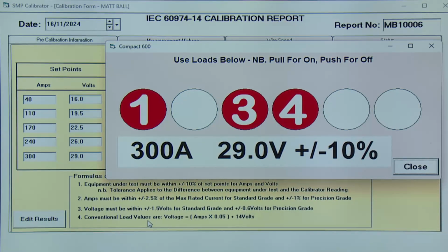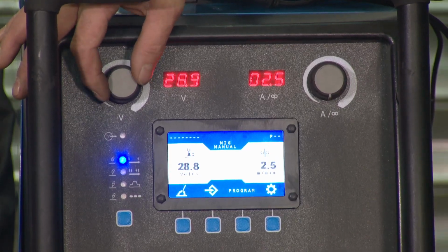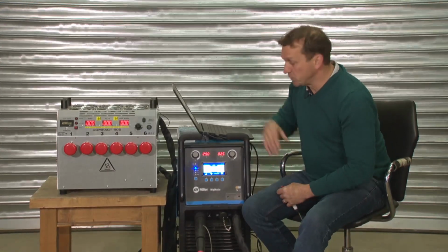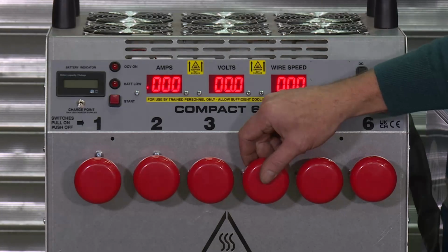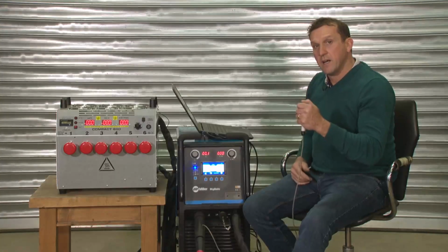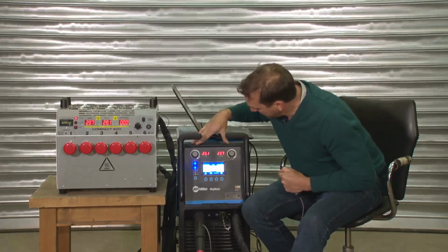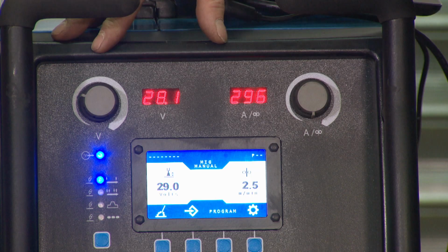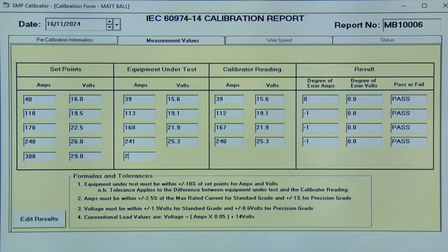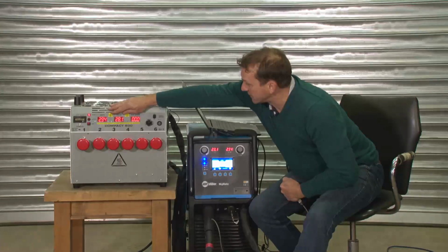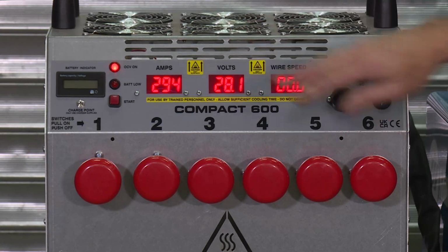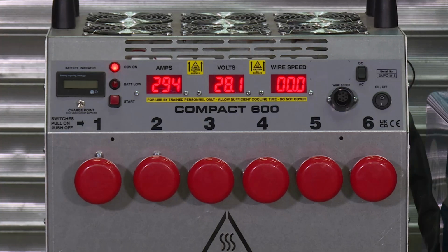And then our final reading, 300 amps at 29 volts. So again, set the welder, 29 volts. And load switches 1, 3 and 4. We energized, finally taking the welder amps reading of 296 amps, 28.1 volts. And then the Compact 600 reading, 294 amps, 28.1 volts.